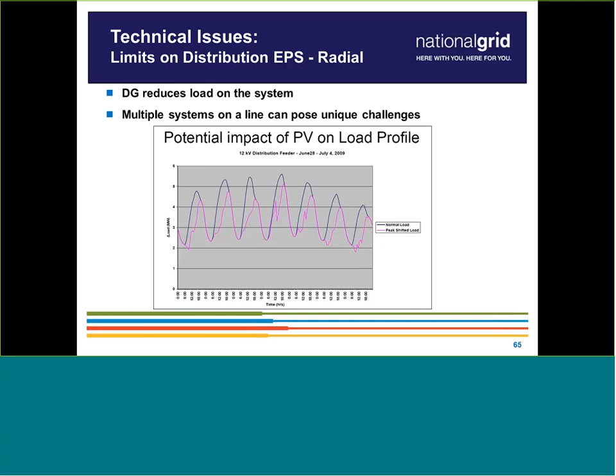It's just more complicated, and this is sort of a zoomed in view of that. We actually do see this where we meter at our substations, which is kind of cool. This is also where we get into flicker problems on these feeders. We get customers complaining sometimes that their lights are flickering in their house on a cloudy day, where we've got 5 megawatts of PV on one of these feeders. That's a problem because it degrades the customer's service from before a PV site went in. So we do try to mitigate that issue, but we try to screen it out before it even becomes an issue on the feeder. We'll tell you in the system impact study if we found a flicker issue, and how we can mitigate it.